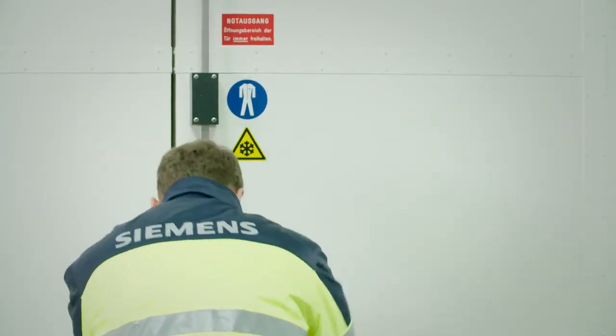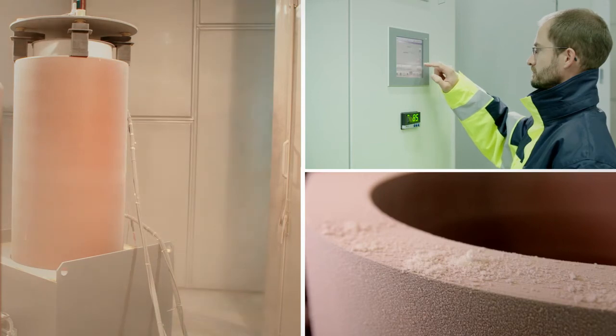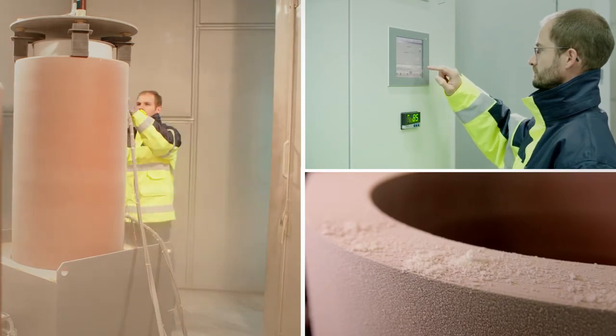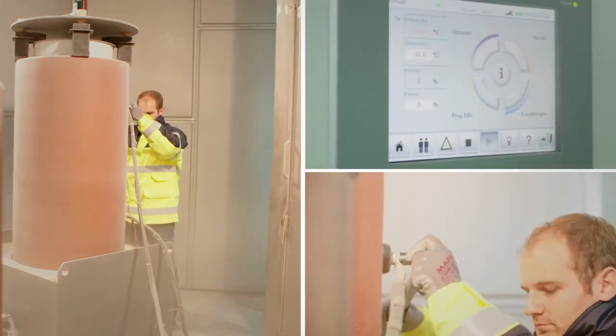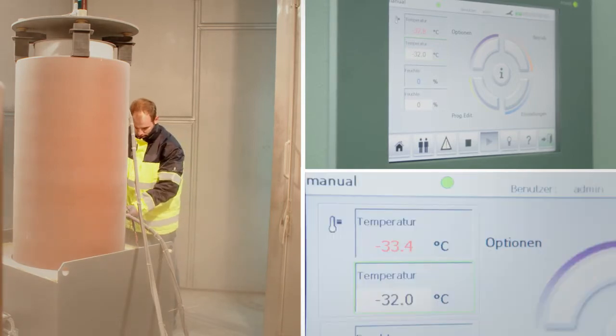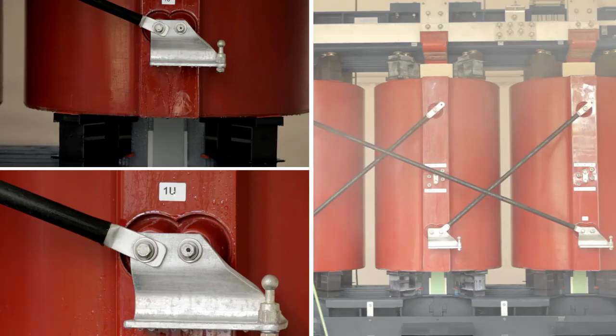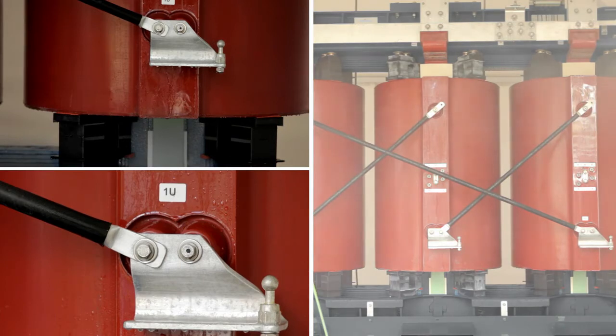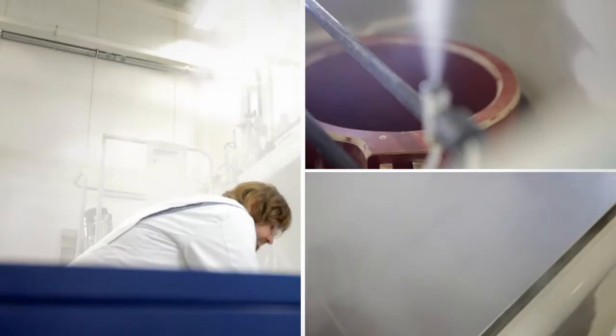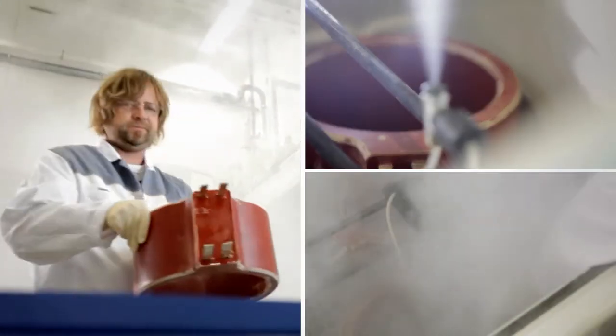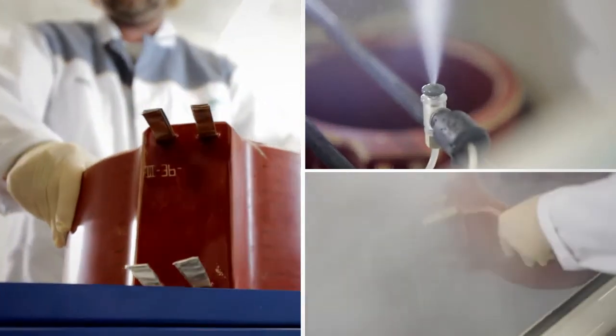Yet, our engineers are always coming up with new tests. Temperature shocks in our climate testing chamber from -25 or even -40 up to +140 degrees Celsius. A voltage test in heavily salty air. Or a tropical test at 50 degrees Celsius and air humidity of 90%.